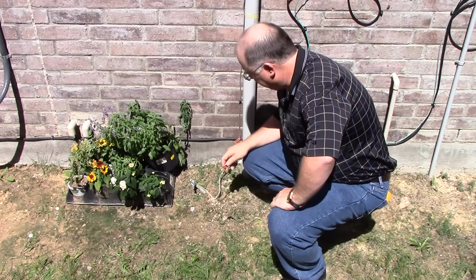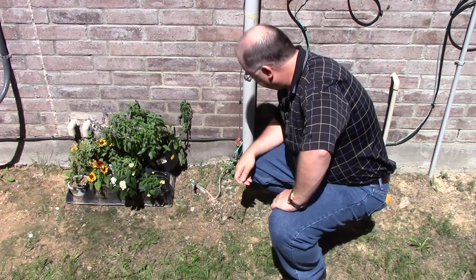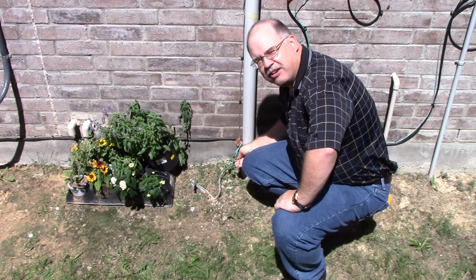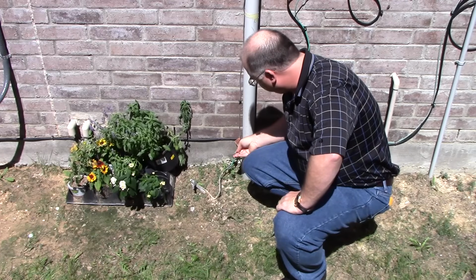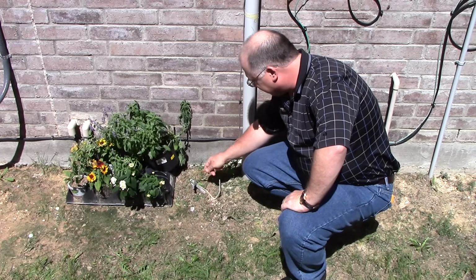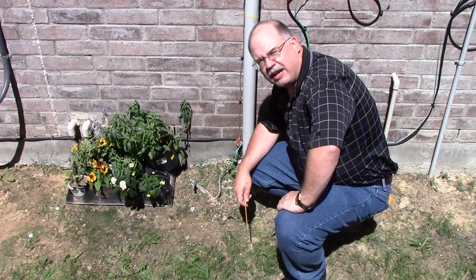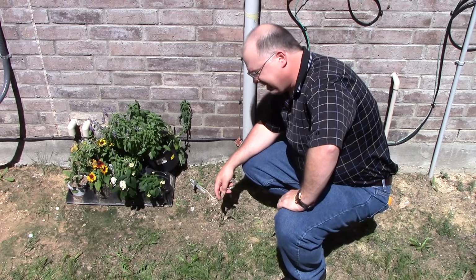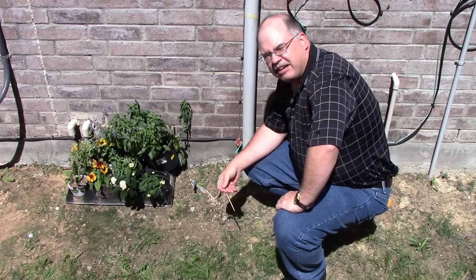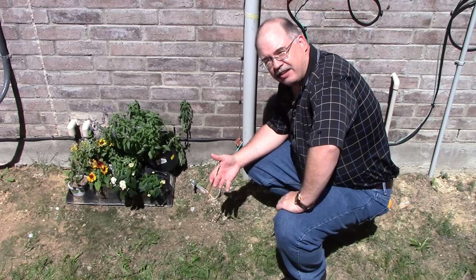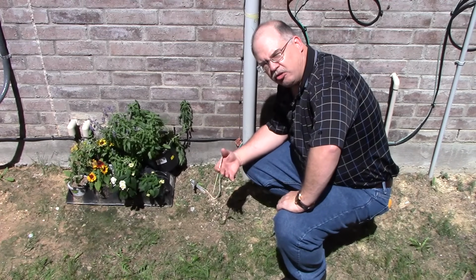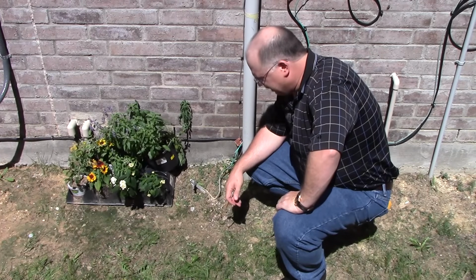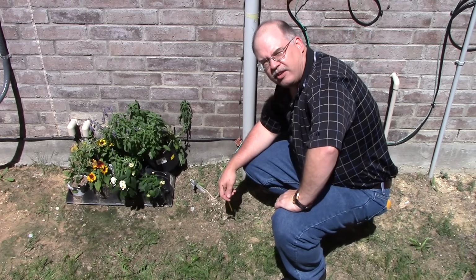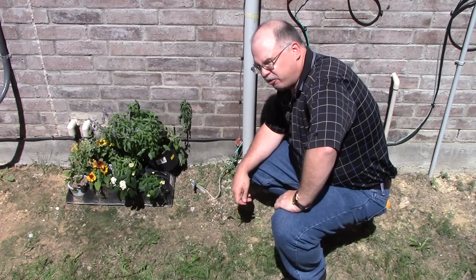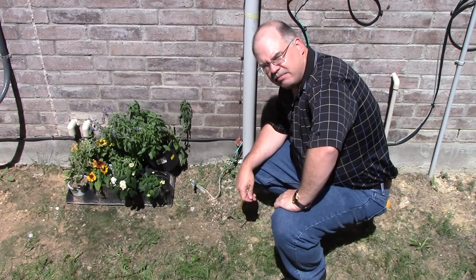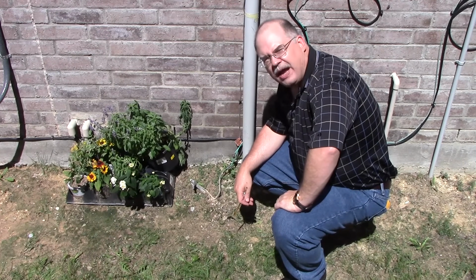Okay, as you can see, we have found the ground rod. It's right here next to where the 4 gauge comes out. So this is 4 gauge copper coming out, and it's connecting here to this acorn clamp that's on this ground rod. Now again, this ground rod was not really necessary because they had a concrete encased electrode. However, they did use it, so when you use it, it does need to be installed correctly. Now, in this case, it was driven at an angle, which tells me they couldn't drive it straight down. It's required to be 8 foot in the ground. In this case, it's not all the way in the ground.